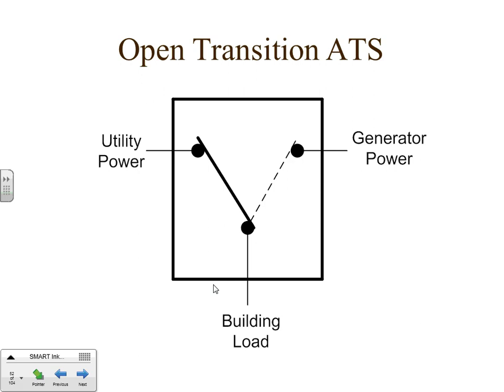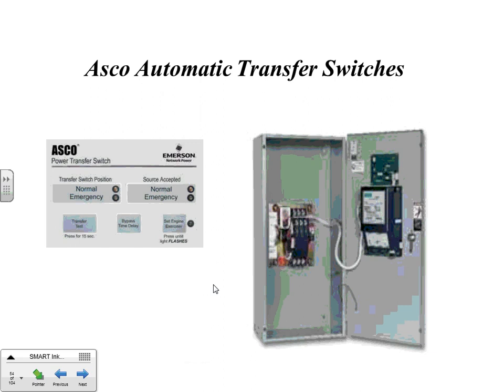This is what I just showed you. This is what they look like. This particular one is an Asco switch, very common brand. Here's what they look like. Basically, the main switching part is back here, the contactor, and it'll have three landing areas. The feed from the generator down here, utility back here, and load here. And it operates just like we showed in the one-line drawing. Pretty simple. It's just got the contactor here and then basically the control over here. And this, I think, is an exerciser clock, which automatically starts and stops the system, and you can choose to transfer or not transfer the transfer switch in your testing times.